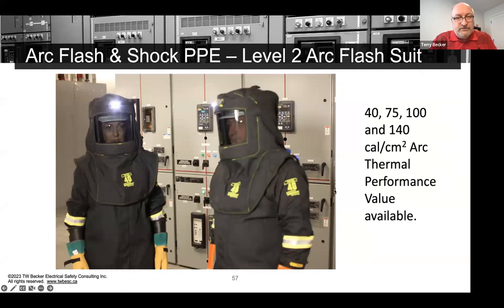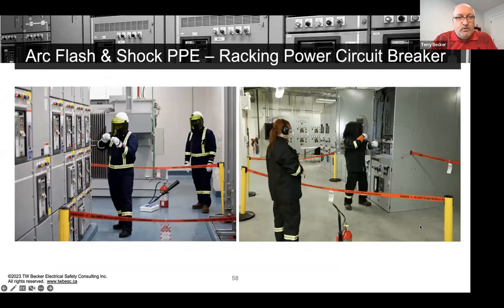And then these are arc flash suits. Again, that's me on the right as the actor. So these are obviously a little more significant, but the technology has changed on these suits. They just continue to go down in weight, fabric weight, and therefore weight to the worker. And just a couple of example pictures, again: racking out a low voltage power circuit breaker with an electrical work zone, and racking out or in a high voltage power circuit breaker on the right with an electrical work zone.